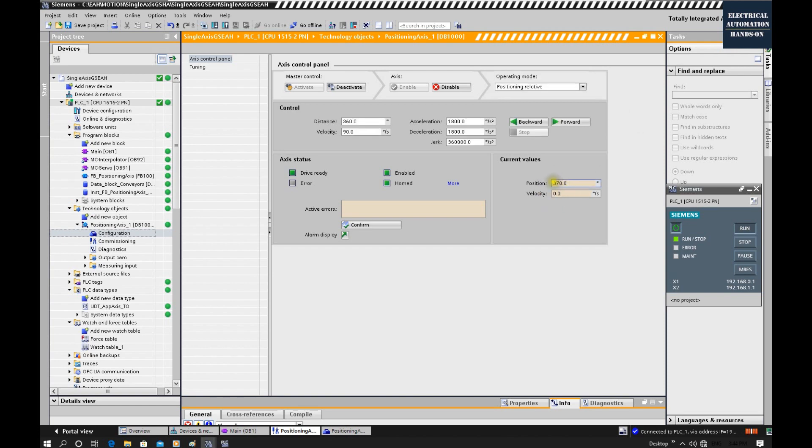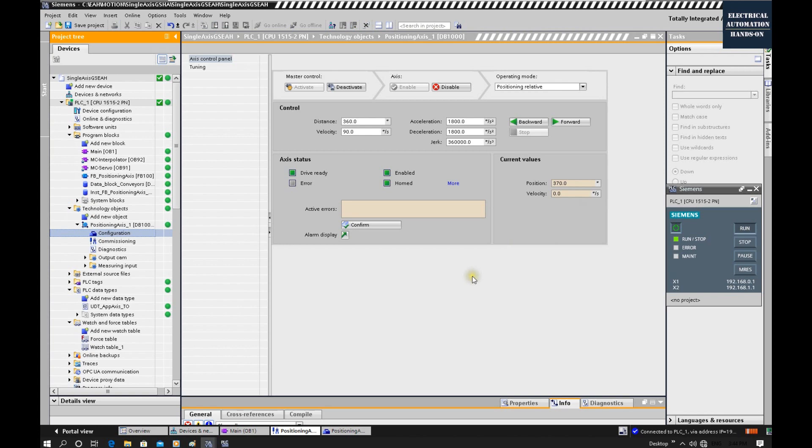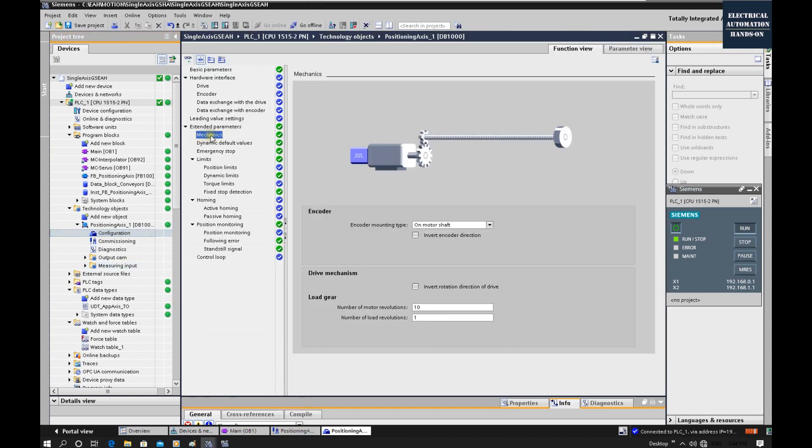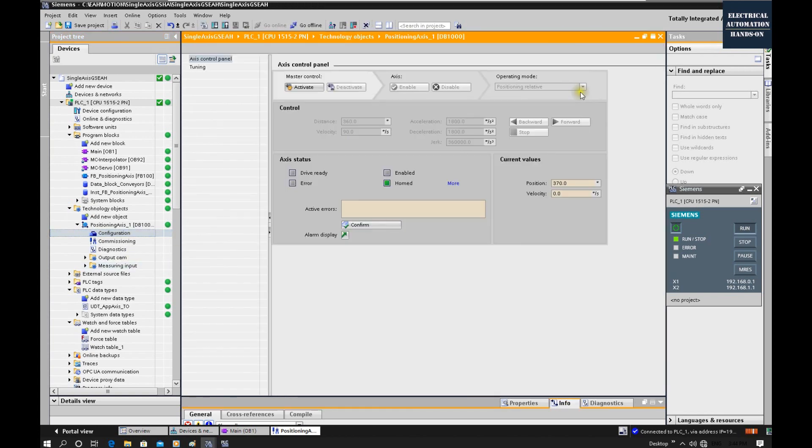Because our home position we started from 10, now the position is 370. If you are controlling one actual servo drive, you need to verify your load actually ran one entire revolution. If you found something wrong, you need to verify some setting within this mechanics here.